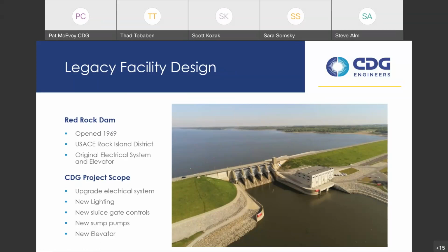Likely moisture got in there over time and eventually shorted out or caused an arcing fault of some sort. The electrical system was dated—they still had original disconnects and panels and that kind of thing. So the project involved upgrading a lot of that, putting in new lighting, and while doing that, updating some mechanical systems: the elevator, new sump pumps, and new controls for the sluice gates.